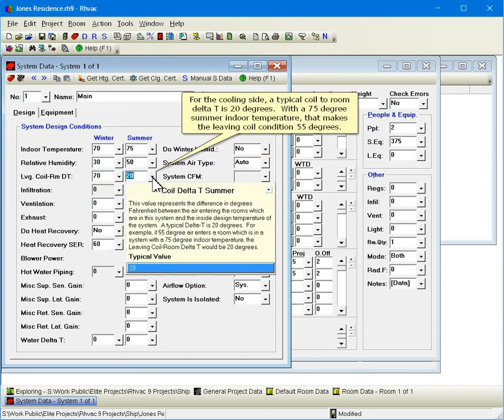For the cooling side, a typical coil to room delta T is 20 degrees. With a 75 degree summer indoor temperature, that makes the leaving coil condition 55 degrees.